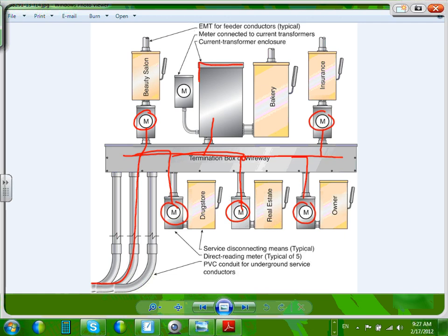But why did that big fat thing set here? Because the load on this building, I think the riser is coming in a second here. The load is very high. So if your load is higher than 400 amp, you need a CT cabinet. That's why they have a CT cabinet here and they don't have it anywhere else.